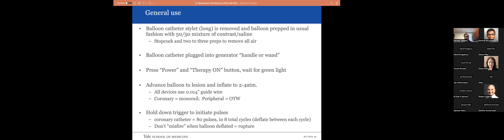Definitely. If you misfire, which is called firing the emitters by pressing the button when the balloon is not inflated, you can rupture the balloon. So be very cognizant of going up on the balloon first, and only to 2 atmospheres initially. The whole point of this balloon is not to injure or dissect the vessel up front. So you don't want to go to high pressure with this balloon at all. So 2 atmospheres for your pulses, 4 atmospheres perhaps, and then ultimately, to show that the balloon is fully inflated, you can go to 6 atmospheres, which is the nominal pressure.